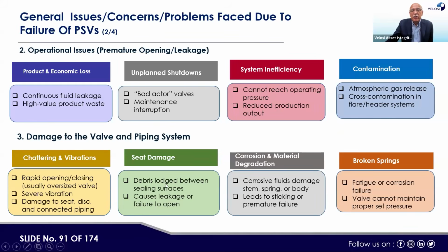Seat damage: debris lodged between the sealing surface causes leakage or failure to open. Then there could be corrosion and material degradation in the valve due to the process fluid, damaging the stem, spring, and body and leading to sticking or premature failure. Then a broken spring due to fatigue or corrosion failure, where the spring of the PSV could fail or get stuck. Then the valve cannot maintain proper set pressure.